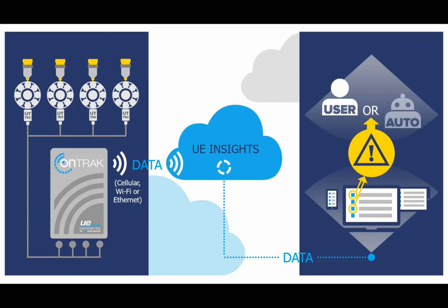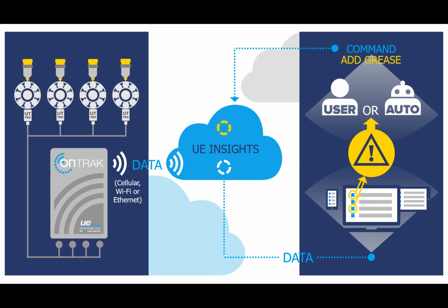Now, at this point, you have some choices to make. Obviously, this bearing requires lubrication. You can go lubricate it yourself using a grease gun and your cell phone, watching that real-time friction, or you can use this Smart Lube feature, which is either a manual or automatic way of sending grease to those bearings. UE Insights uses a proprietary algorithm designed specifically for ultrasound guided lubrication best practices to properly and sufficiently lubricate that bearing.